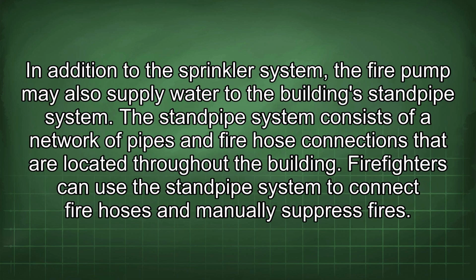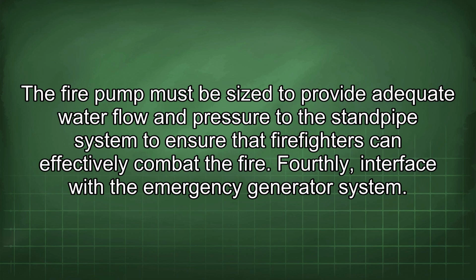In addition to the sprinkler system, the fire pump may also supply water to the building standpipe system. The standpipe system consists of a network of pipes and fire hose connections that are located throughout the building. Firefighters can use the standpipe system to connect fire hoses and manually suppress fires. The fire pump must be sized to provide adequate water flow and pressure to the standpipe system to ensure that firefighters can effectively combat the fire.